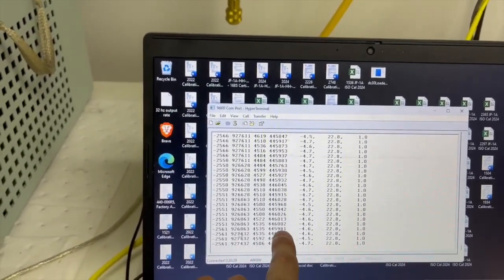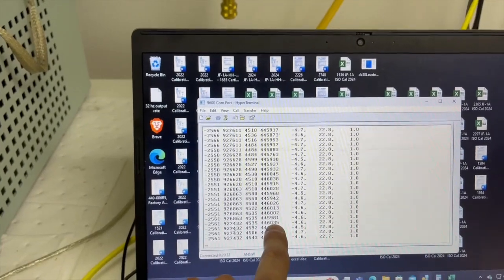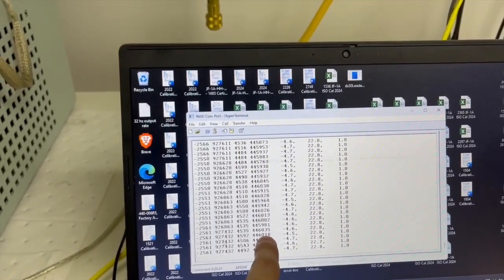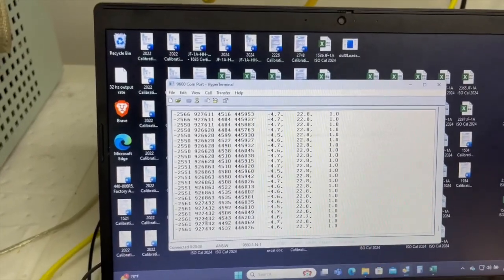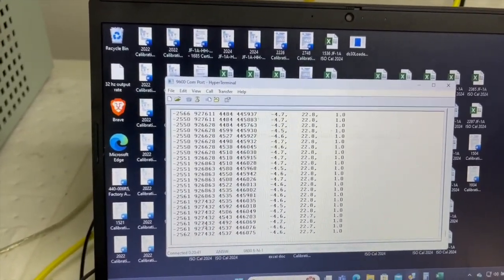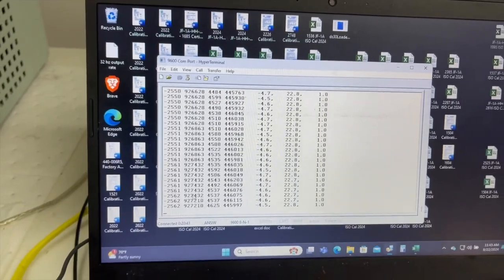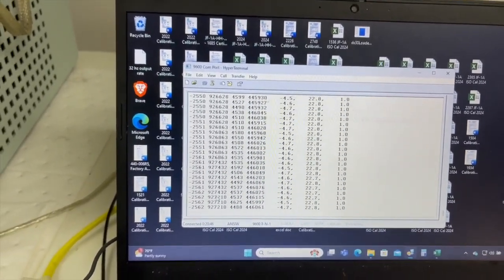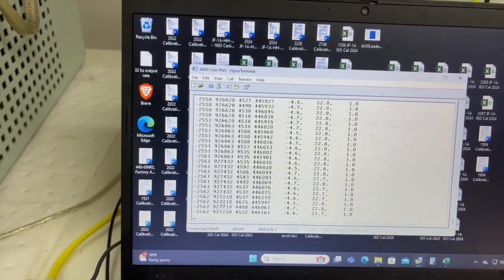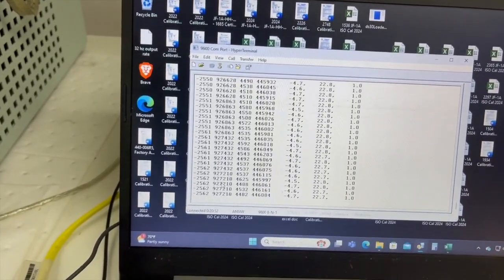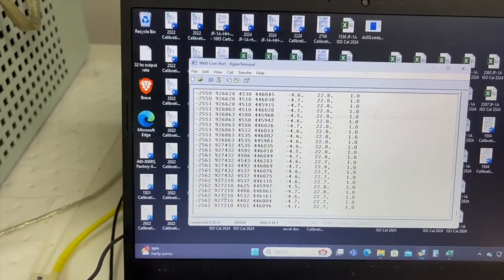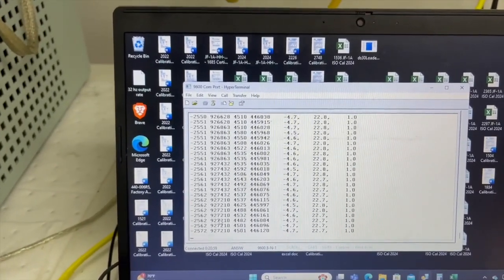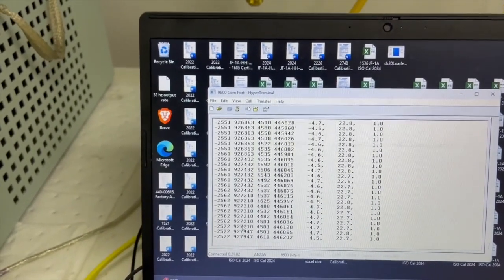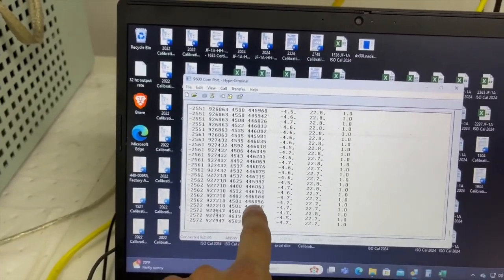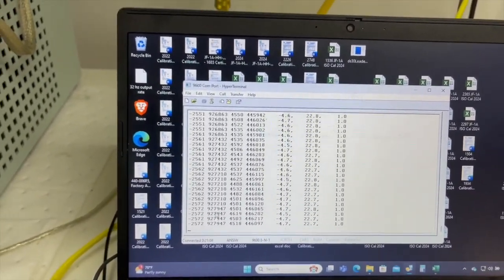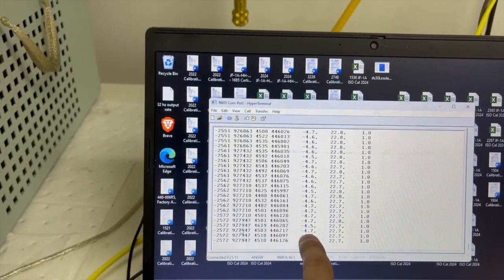This right here is your temp counts, and those should be between 400,000 and 600,000, unless you have an ATEX sensor, and then those should be somewhere around 250,000 or so. If you have the ATEX version of the inline sensor, that number will be roughly 250,000. But if you have the FM version, which is what we're calibrating, then this is between 400,000 and 600,000 for this number here. And then this should be between minus 10 and 20.